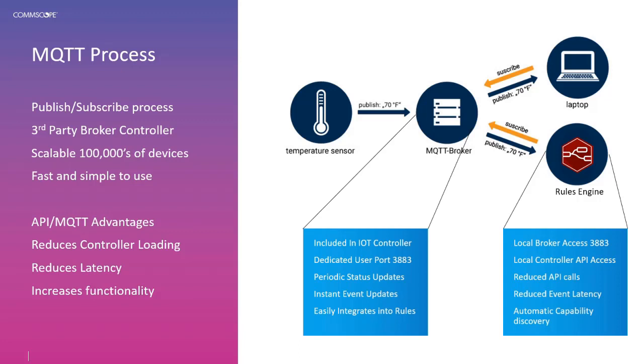This also allows us to do automatic device capability discovery in conjunction with the MQTT process within the controller. The IoT controller will publish all the information about a sensor to the rules engine so it can build up a local database of all the capabilities of that sensor. When an event change is sent, we'll be able to look up exactly what that sensor data is — whether it's a door contact, temperature, or humidity — using a combination of the status information sent and the event notification.